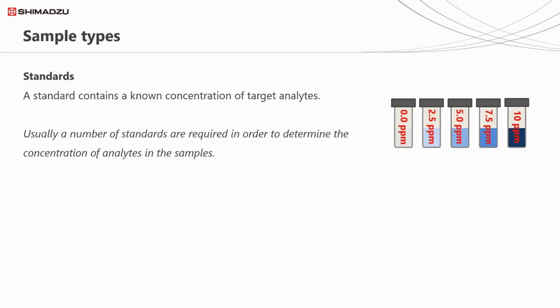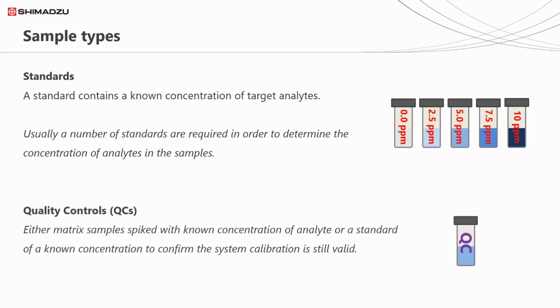Standards contain a known concentration of a target compound or compounds. If we want to calculate the concentration of analytes in our unknowns, we'll likely need a number of standards, each at different concentrations. In many regulated environments, you might also come across quality control or QC samples. These also have a known concentration in them. The difference with QCs is that we analyse them as if we don't know the amount, and then compare the reported concentration with the known concentration to determine whether the GC system is reporting within specification.